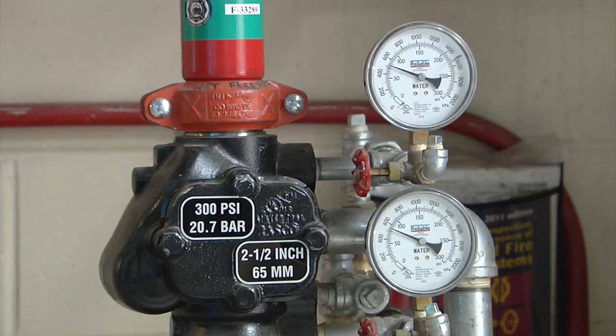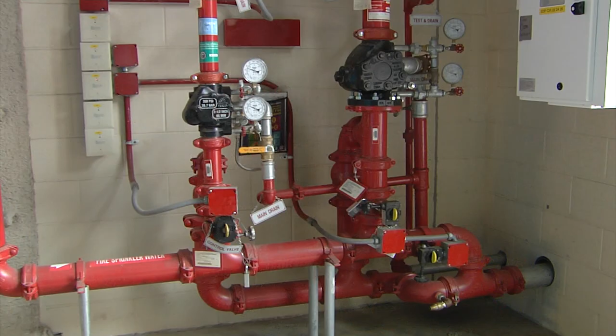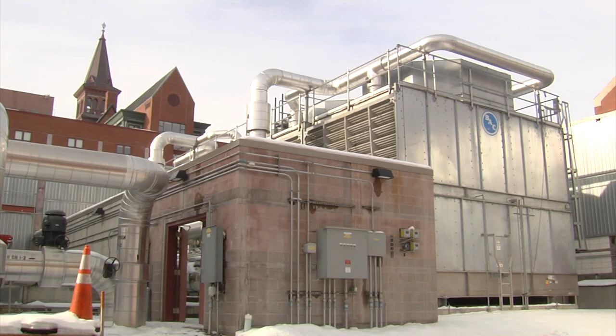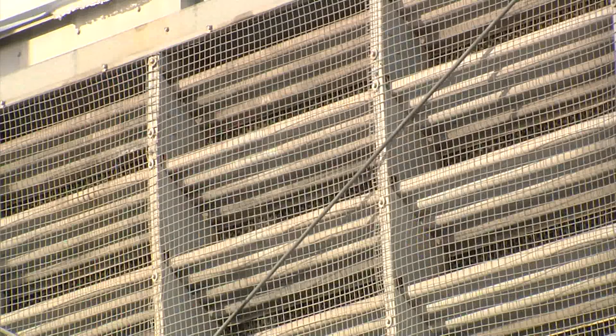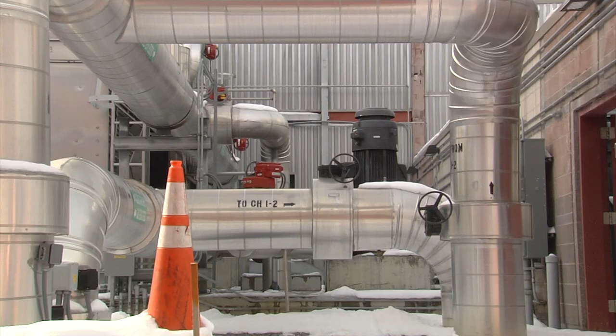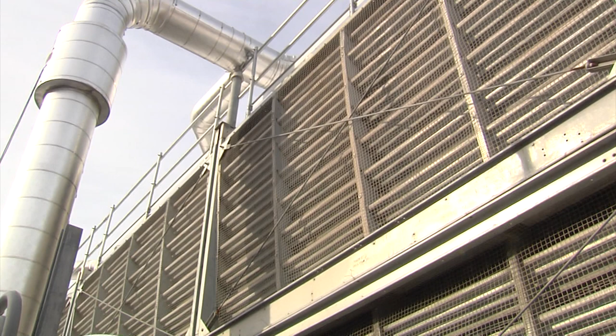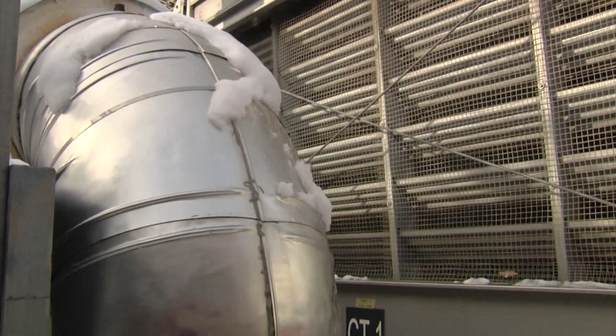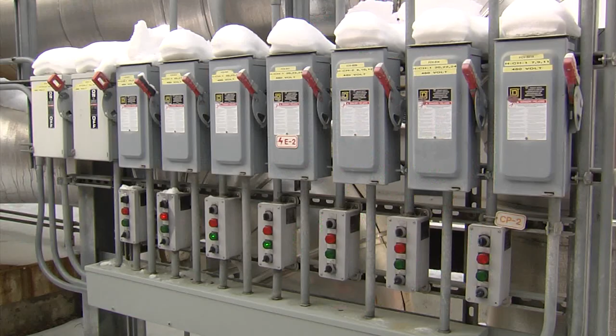Well, first of all, by having a central plant, we reduce our carbon footprint by about 30%. The efficiency of having the equipment in an industrial manner here at the plant eliminates the need for building-centric systems, so you don't have to install as much capacity. When we do projects at the plant, it's so large that it has a big impact on our carbon footprint. For instance, when we built this new addition for central cooling, we put in what's called a free cooling system, where we use the outside air temperature to cool the chilled water sent out to the buildings, so we don't have to compress the refrigerant. In the shoulder months, when it's like 45, 50, 55 degrees and there's still cooling needs in the building, we can use the outside air temperature to cool the buildings.